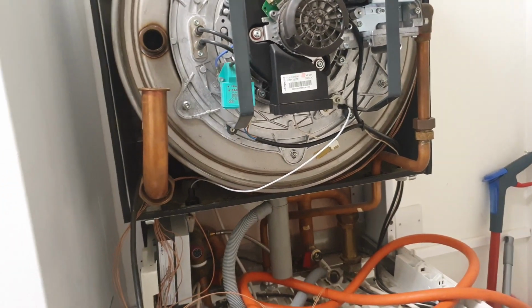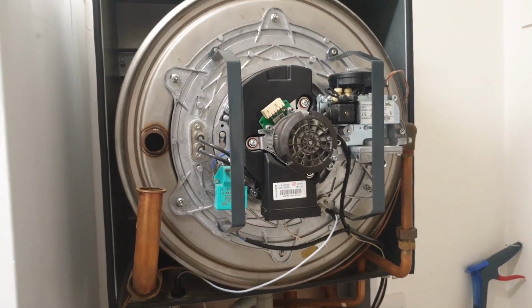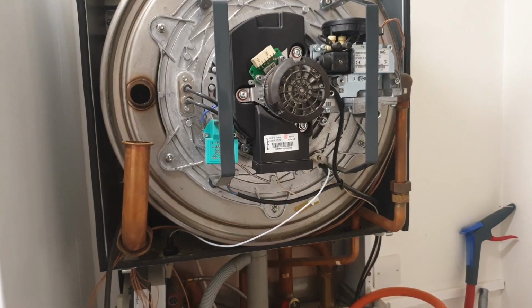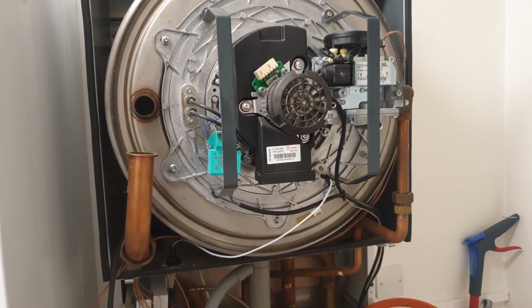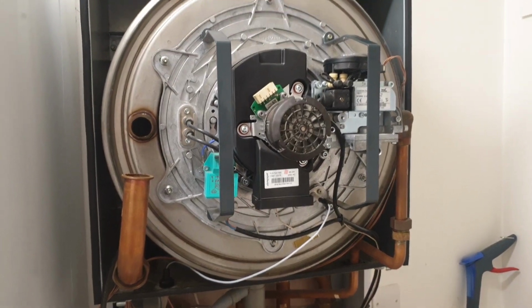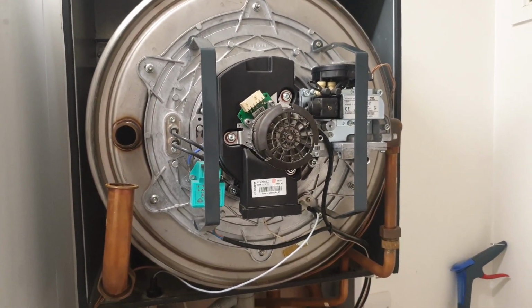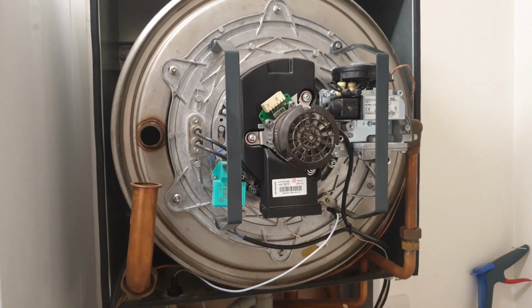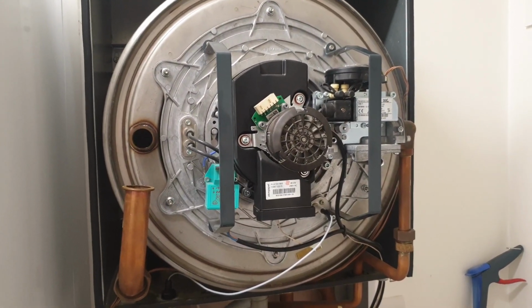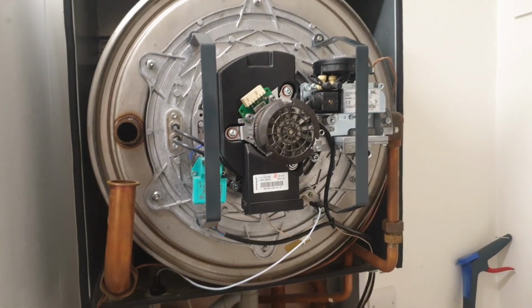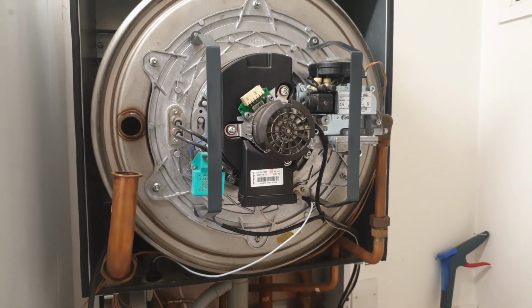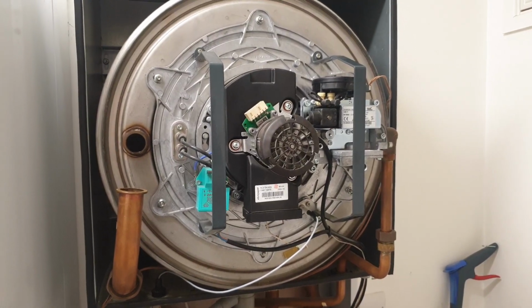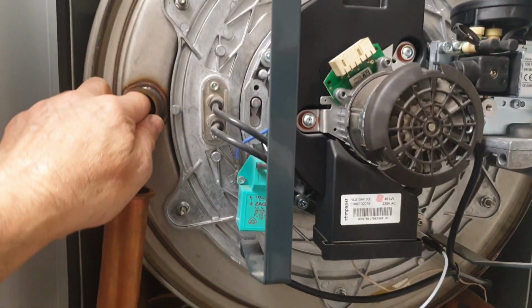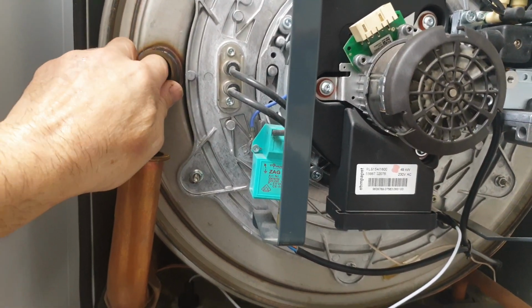Now, this is my theory. I've got no evidence. It's pretty much a seat-of-my-pants theory that in a stainless steel heat exchanger, stainless steel isn't the greatest of conductors. So I believe that there's localized heating between the flame and the first stainless steel surface that's exposed to the flame, the hottest part of the heat exchanger in effect. And I believe that the contaminants in the water coming back from the system get cooked on that face into this scale deposit, and this takes place in the heat exchanger.